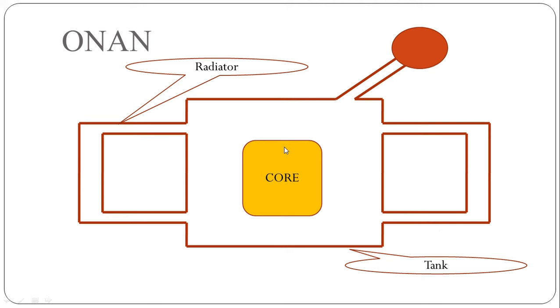As the volume of transformer oil increases on heating, it becomes less dense. This hot oil moves towards the surface of the transformer tank, rising towards the top. At the top of the transformer tank there is an upper valve which connects the radiator to the tank. When the oil reaches the upper surface, it enters the radiator through this upper valve, spreading through the radiator tubes, which increases the surface area for convection.